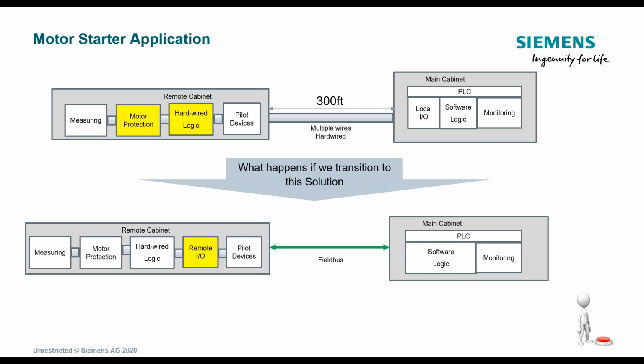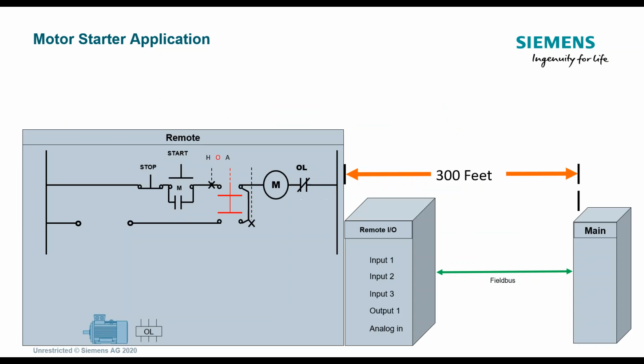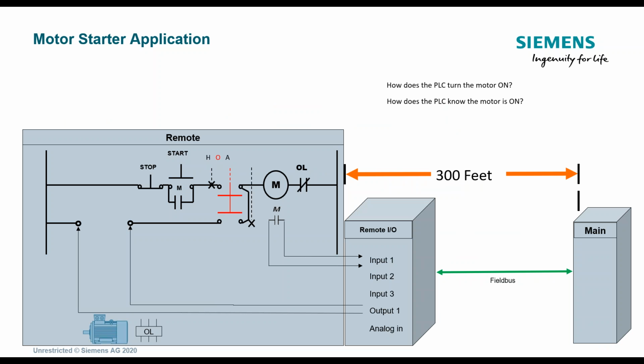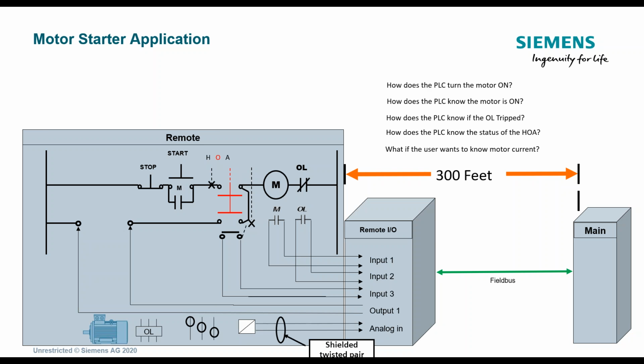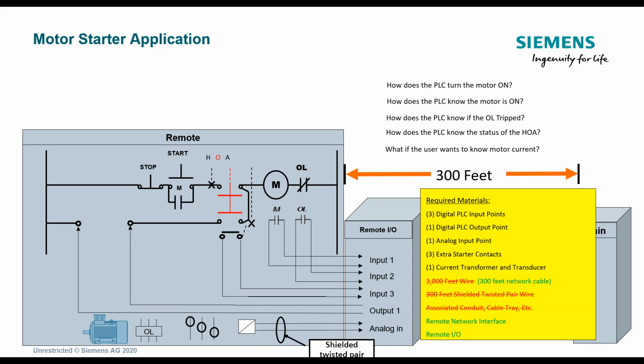Okay. So now we're into the field bus. So we remove all the multiple wires, hardwired and landed. Okay, so now we introduce the field bus. Here's the remote I/O, and here comes the same scenario. But now we get rid of all that wiring, and we get rid of the conduit, because now we're bringing in a field bus cable, which could be Profibus or Profinet, an RS-485 communication protocol, or TCP/IP protocol. So we're reducing that.